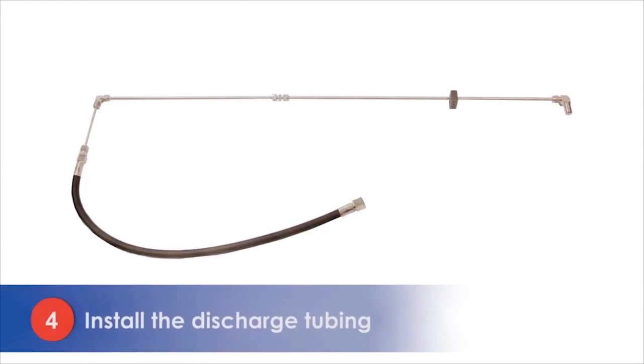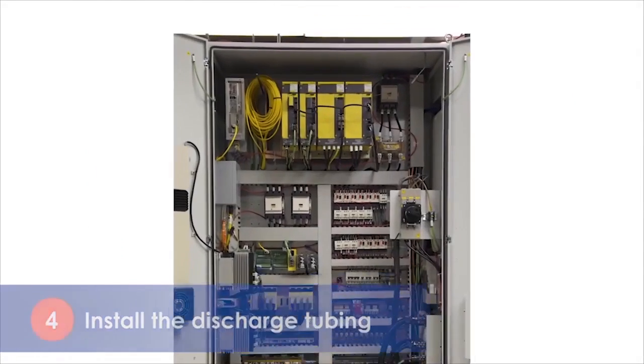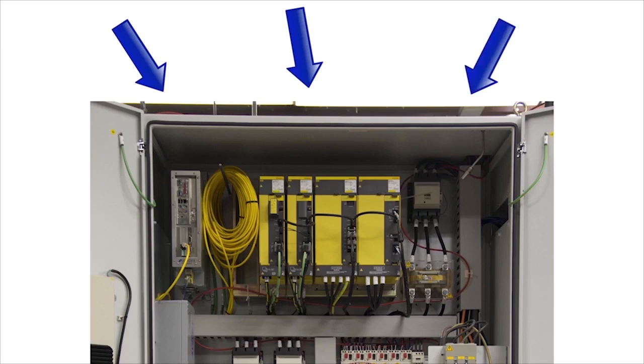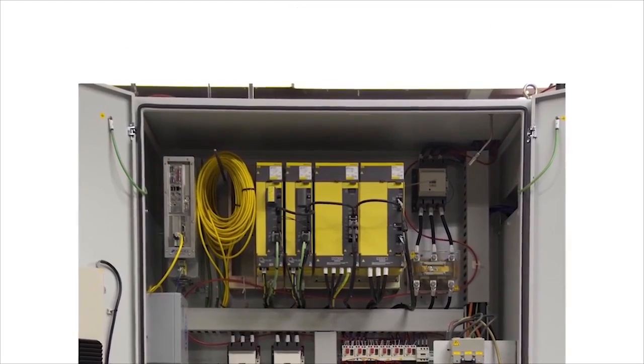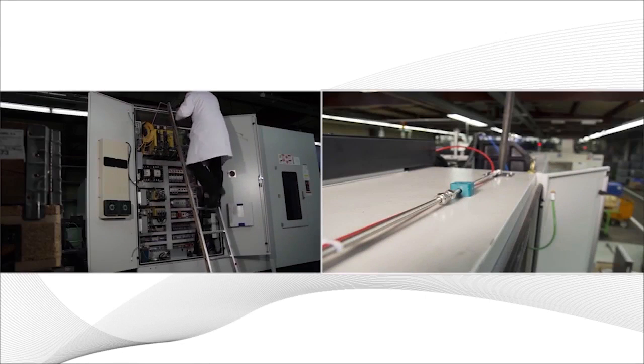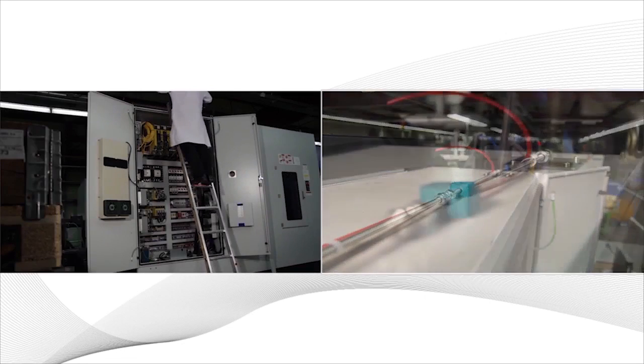The discharge system consists of the discharge tubing, fittings, and the nozzle. Start by identifying where you would like to place the nozzle. Ideally, it should be placed on the enclosure ceiling in the center, or if that is not practical, then on the side pointing towards the center. The discharge tubing is normally installed outside the cabinet.